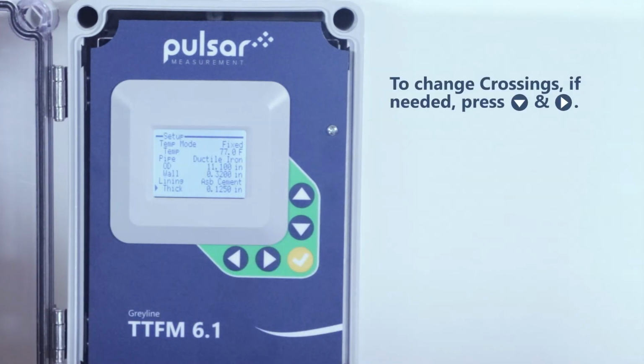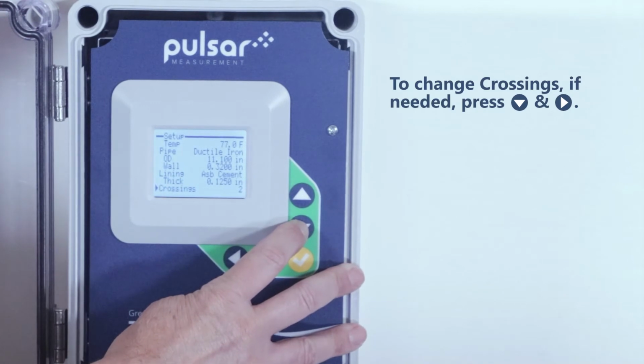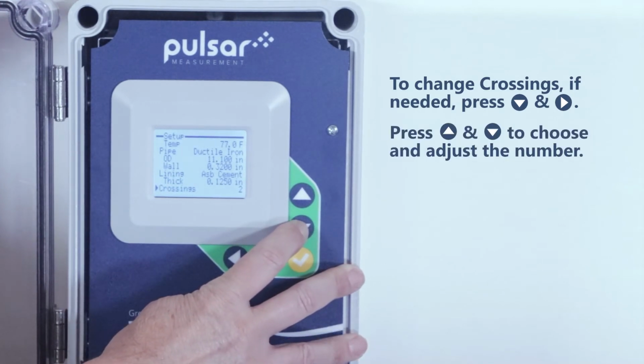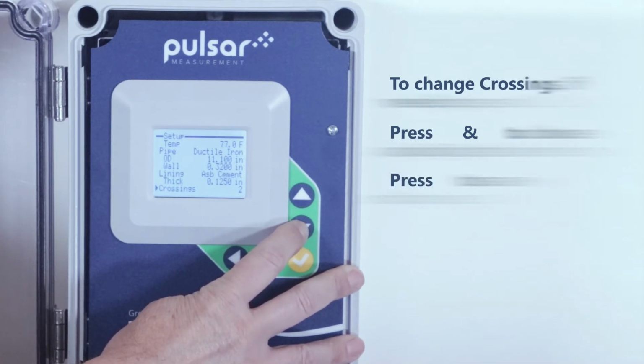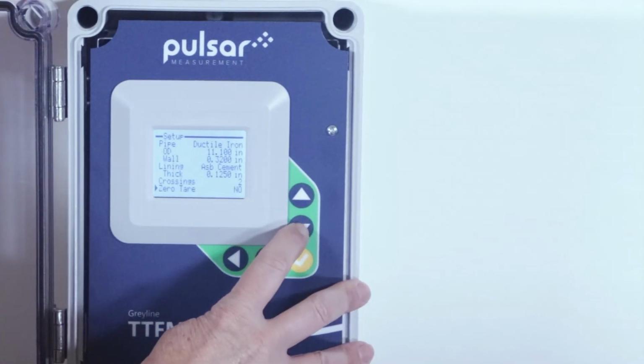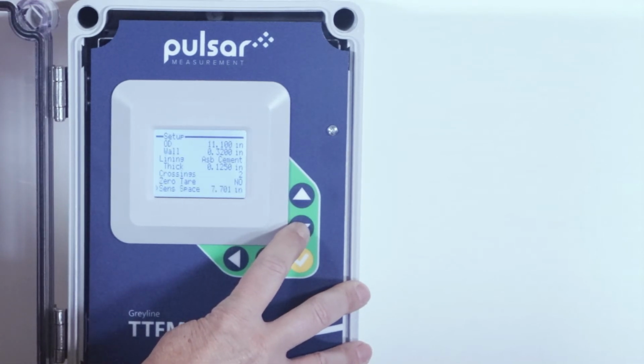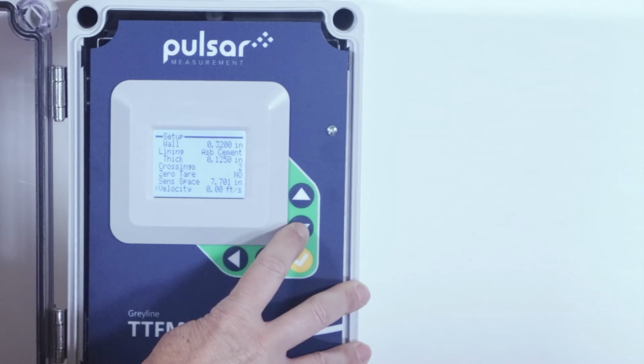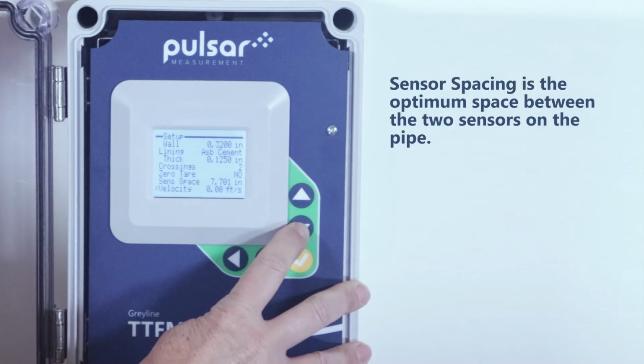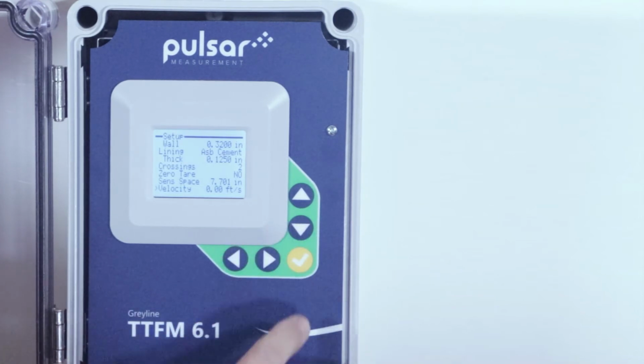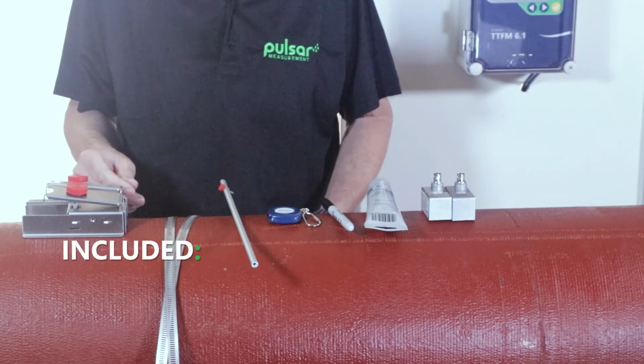Our next step is to hit the down arrow button until crossings appears. This is the optimum number for this application, 2 crossings. As we continue to scroll down, zero tare is not in use. Finally, we'll come to the sensor spacing. This is the optimum space between the two sensors on the pipe. In this case, optimum spacing is 7.701 inches. Now it's time to install the transducers.